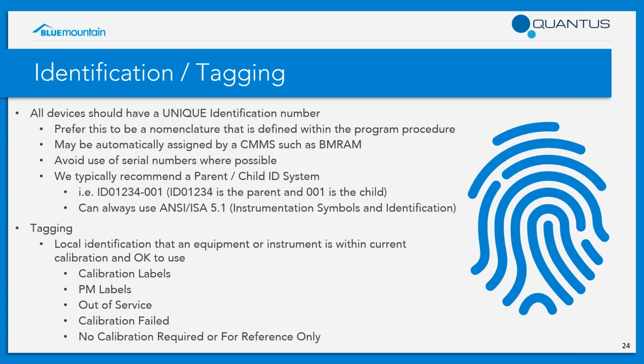A lot of companies, when they get started, don't have an ID number system, so they just default to the serial number. It's a difficult practice because not all serial numbers may be unique from manufacturer to manufacturer, and in some equipment, they may not exist altogether. So whatever system you decide to go with for your identification system, make sure it's documented within your master program SOP, make sure people are trained on that, and that it's readily available for reference as you're adding instruments to your program.